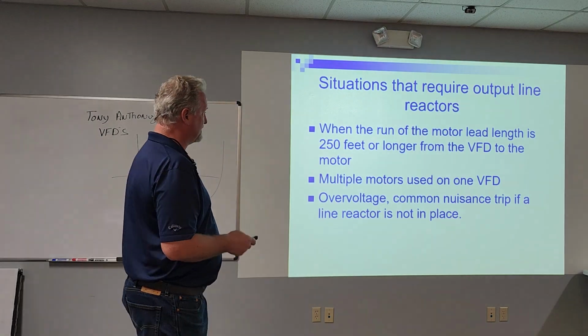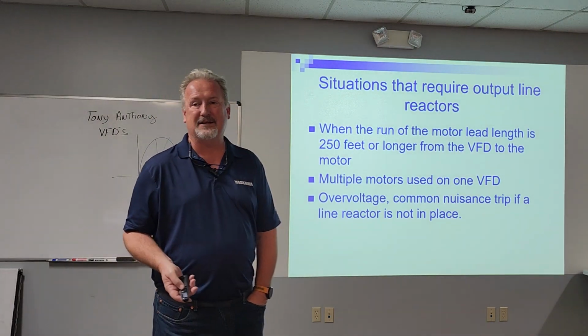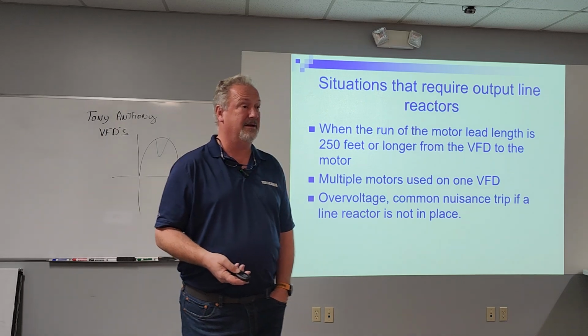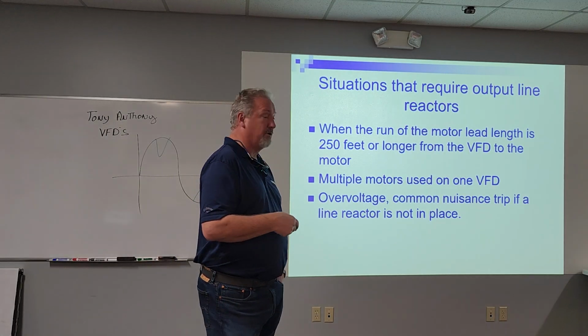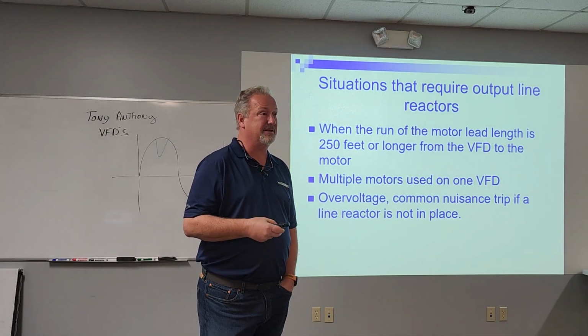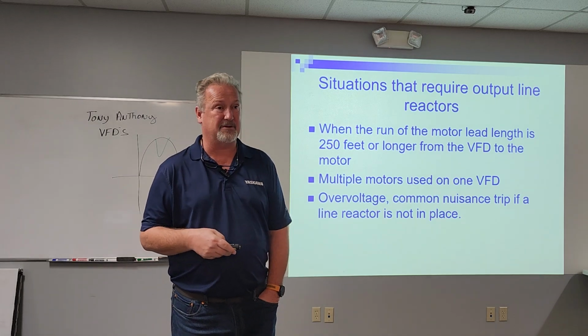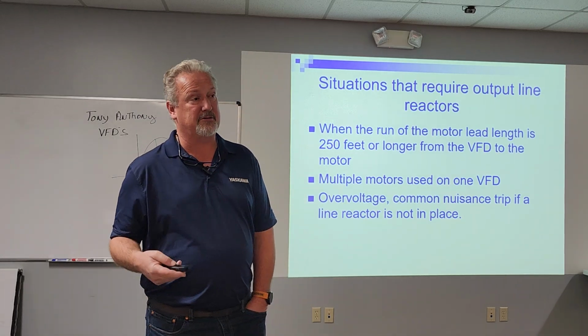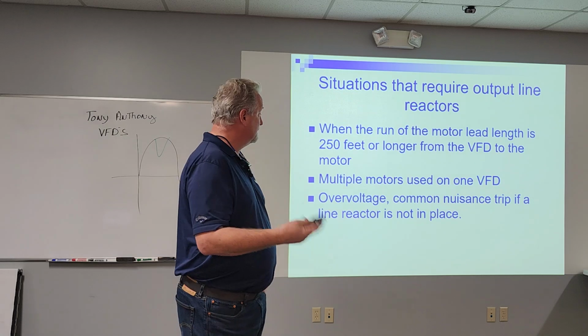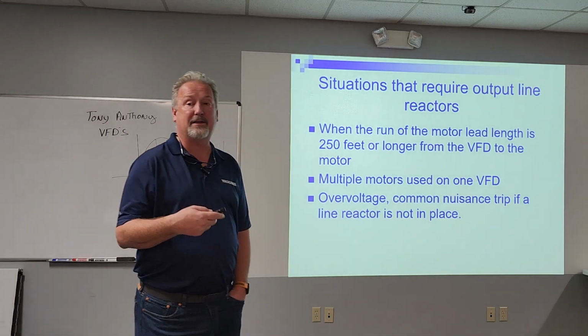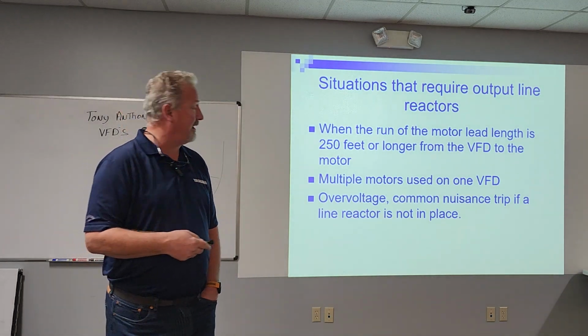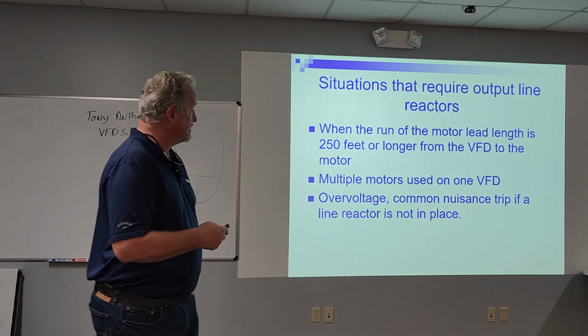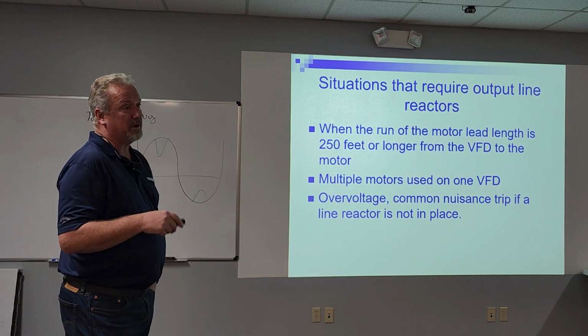It's the same thing with motors. There are some cheap motors out there that you can get. They meet the spec of a motor, but once you start getting more than about 100 foot, 150, 200 foot, you're going to have troubles with that motor. You may burn the motor up. So it's really motor dependent. You really need to talk to the motor manufacturer about what they need at what distance from the drive. We use a line reactor if we run more than one motor off a drive.